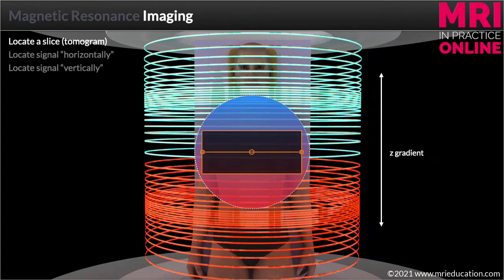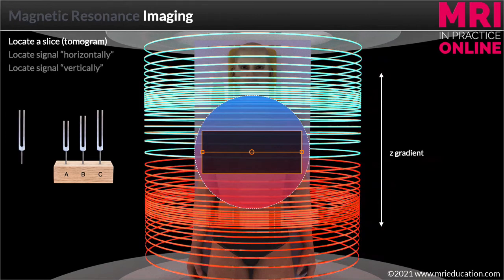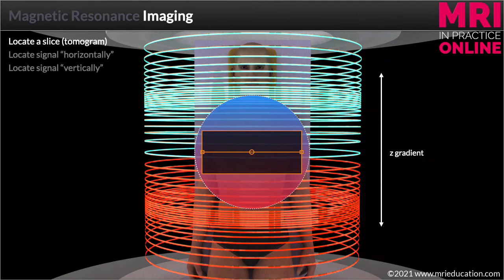Staying with the concept of resonance for a minute, tuning forks are a good example of how resonance works. If two tuning forks share the same frequency, there can be a transfer of energy from one to the other by resonance. Because precessional frequency is proportional to flux density, we can represent the resonant frequencies of the spins along a gradient with imaginary tuning forks of different sizes. Let's imagine that there are five possible slice positions in the data set — they will all have different frequencies from the high to the low end of the gradient.